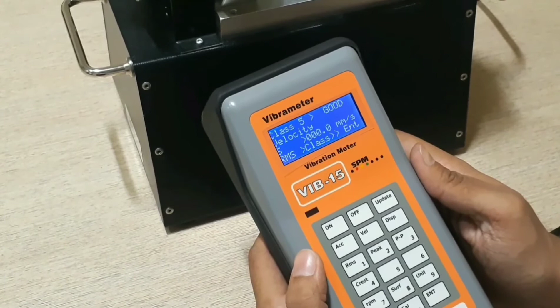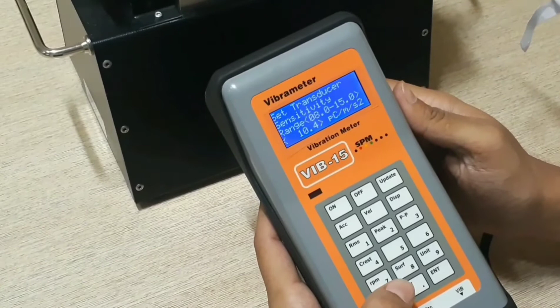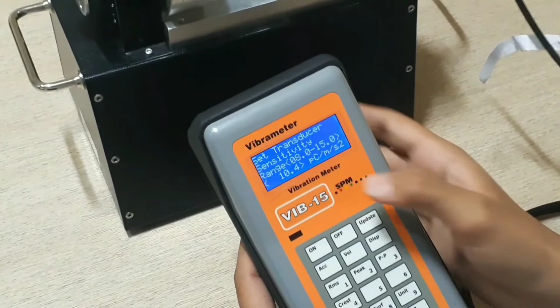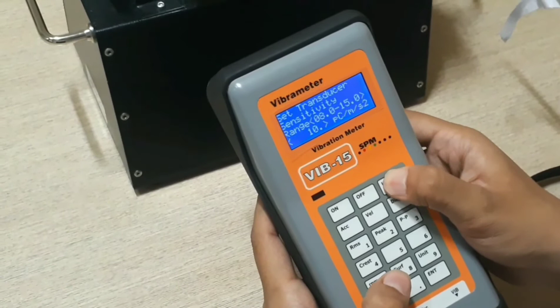In this velocity RMS screen, right now I am pressing cal. With the help of this cal, we can set the transducer sensitivity range. Right now this sensor has a 10.4 sensitivity range, so I have set it to 10.4. According to your transducer, you can set it over here. By pressing this update button, as you can see here, you can change the values.